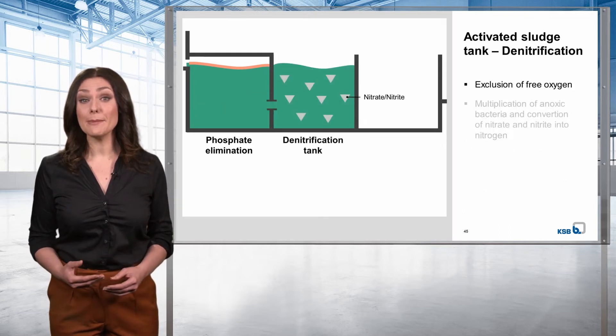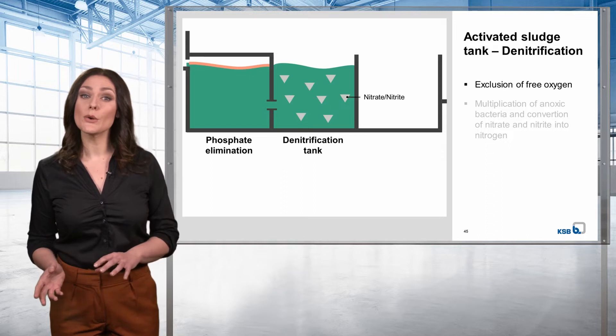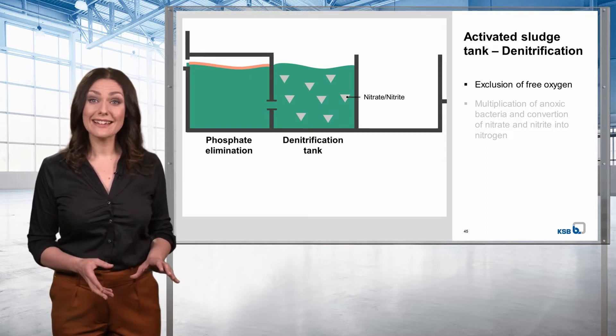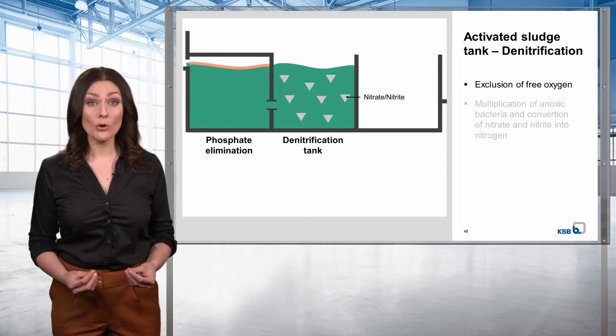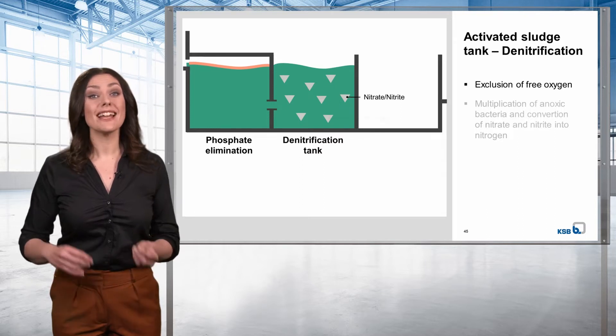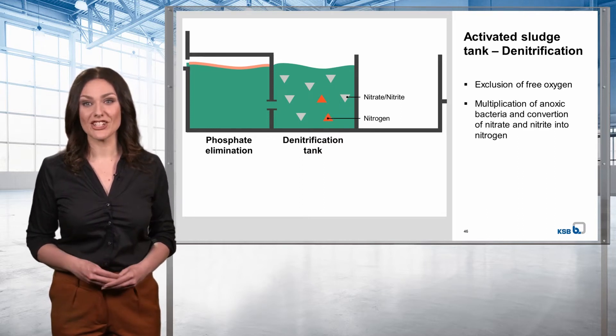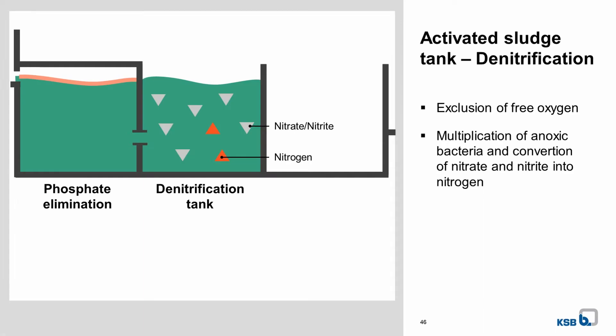When the phosphate has been eliminated in the first stage, the water flows into the so-called denitrification tank. Here, it is the anoxic bacteria that enjoy optimum life conditions. With free oxygen being excluded, anoxic bacteria thrive and multiply, and they biologically convert nitrate and nitrite into nitrogen.